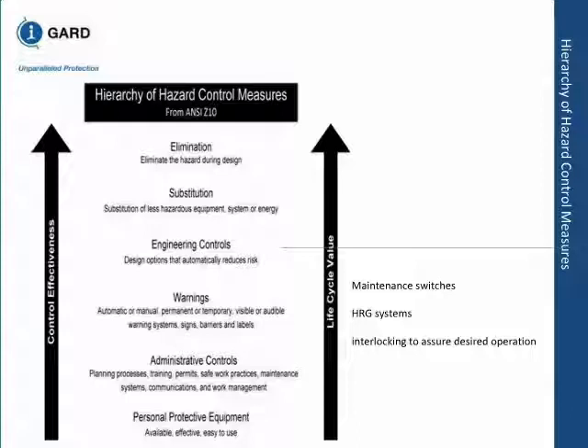Of course, all of you are shaking your head, I won't make a mistake, but people who are working for you might make it. So you interlock it, so that you cannot close a tie breaker till one of the main breakers is open. High resistance grounding system: you can give a definite time that if you don't clear within a certain time, it will go in a trip mode.